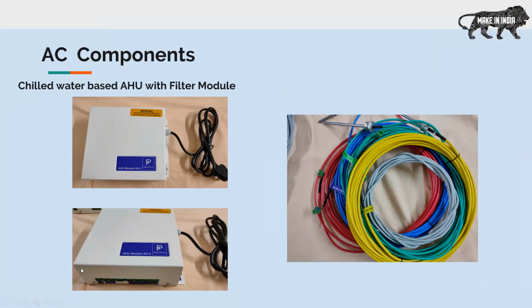On the left-hand side of it are four status input ports. On the right-hand side, two controlling ports, one for AHU on/off, and one for filter monitoring. This white port here is the RS485 communication port, through which I can add additional sensors or modules such as a CO2 sensor, an additional pressure sensor, or a duct damper control module. And these are all the sensors which we manufacture.